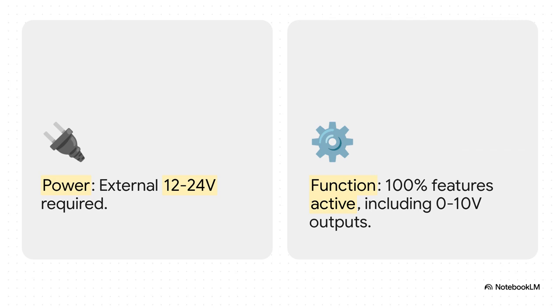Think of this as the full power, all features unlocked setting. Yeah, it needs an external 12 to 24 volt power supply, but in return, you get everything. All the data over the Modbus network, plus it activates the 3 analog 0 to 10 volt outputs at the same time. The whole shebang.